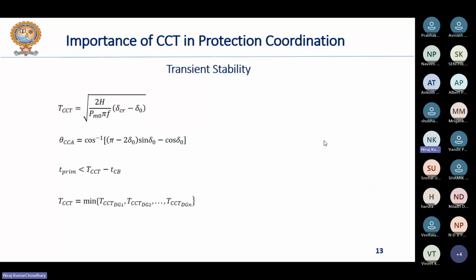Whenever such a condition arises, or whenever there is a high penetration of SBDGs connected to the system, the inclusion of this CCT, that is critical clearing time, is very important, and that should be incorporated in your relay coordination problem. Here you can see the expression of critical clearing time, that is T_CCT. It depends upon different factors like H, the inertia constant of the SBDGs, then P_m0, which is the mechanical power input to the machine, then f is the frequency of operation, delta naught is your initial power angle, and delta critical, delta_cr, is your critical power angle, right?